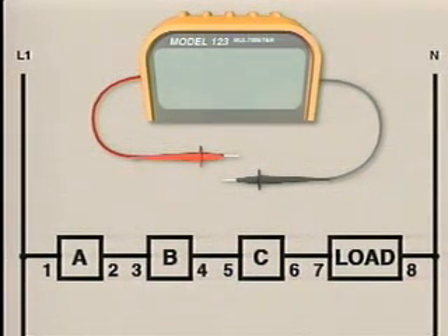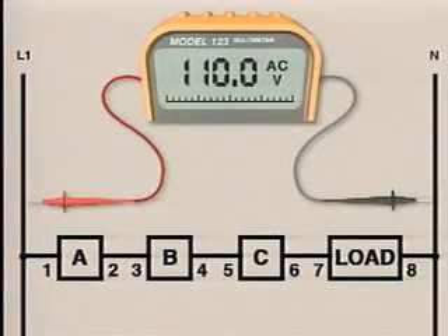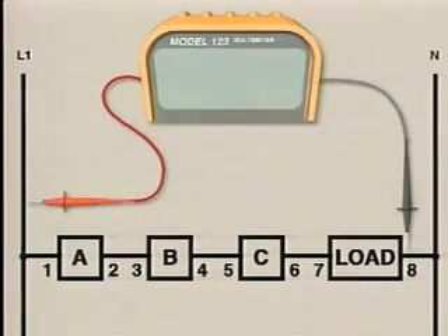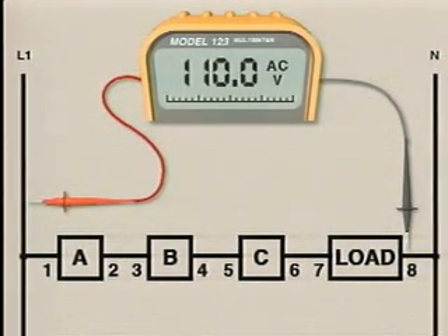Troubleshooting a problem in a circuit using the serial method involves checking the components in sequence, one at a time. This way, you can eliminate one component at a time as a possible cause of the problem. Although this method is logical and effective, it can be very time-consuming. For example, let's assume that there's a problem somewhere in this circuit, and that we know the circuit has the proper operating voltage. In this example, we'll use test point 8 as a reference point. To make sure that the reference point is good, we'll measure the voltage between L1 and test point 8. The voltmeter indicates full line voltage, so the wire connecting the load to neutral is good and can be eliminated as a possible cause of the problem.